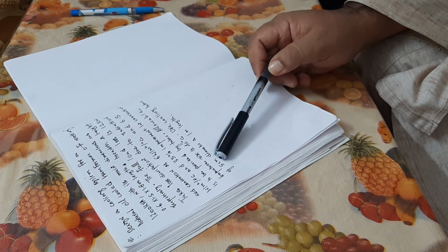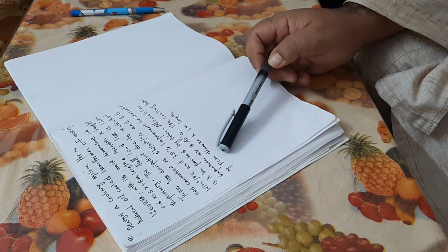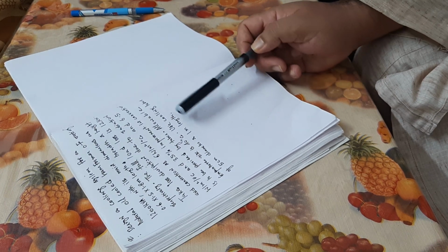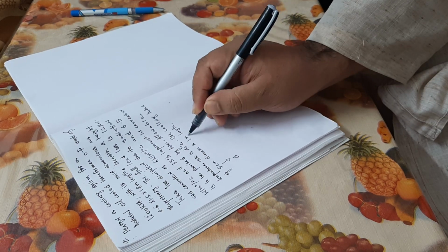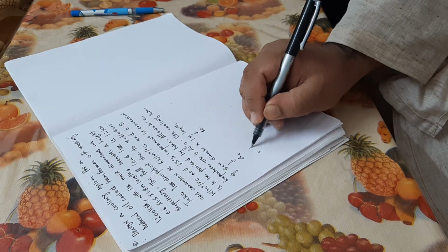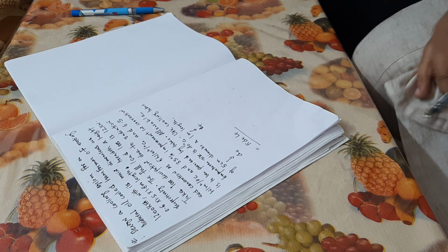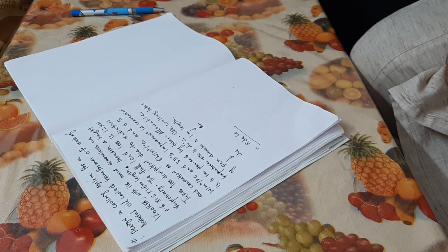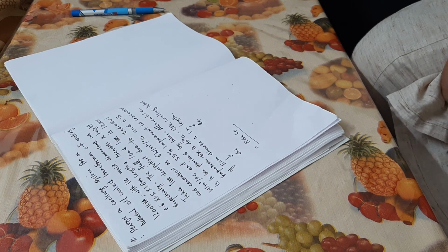So the allowable temperature rise is 40 degrees. Use cooling tubes of 5 centimeter diameter and 1 meter length. So this will be your dt, and this would be your LT. So the area of a cooling tube, if you have to calculate, would again be pi dt LT. So again, before directly jumping into that, let's first see what values we are given here.